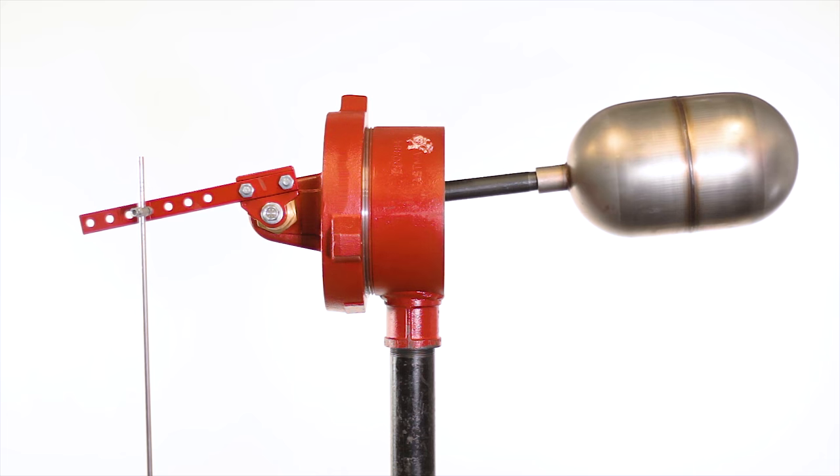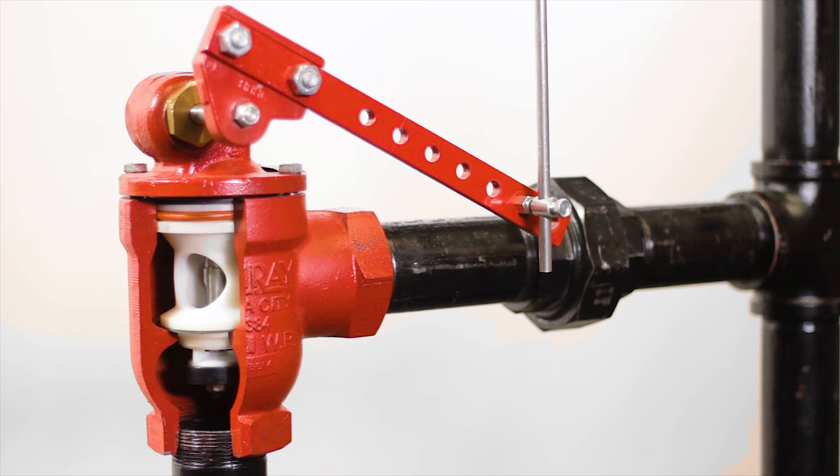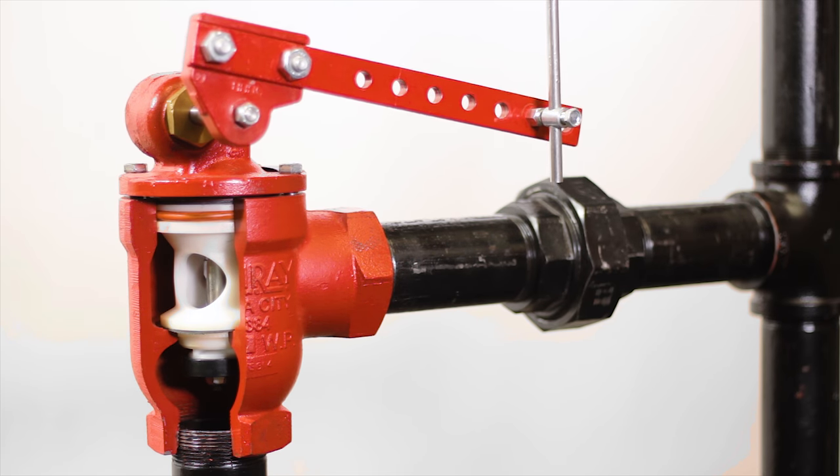As the liquid level in the vessel begins to fall, the float moves downward, forcing the trunnion lever upward. This pulls the valve lever up and closes the valve.